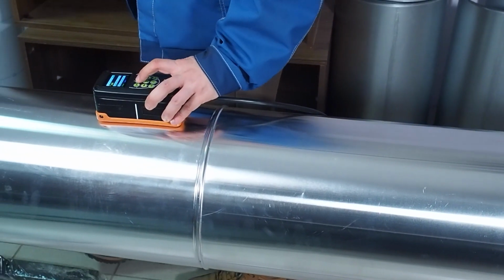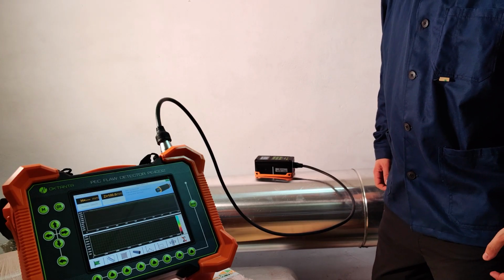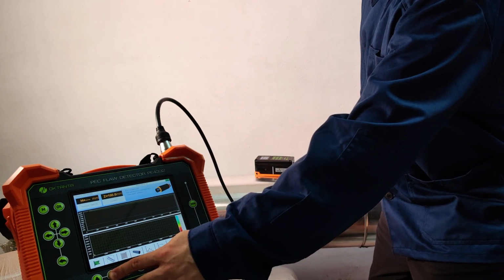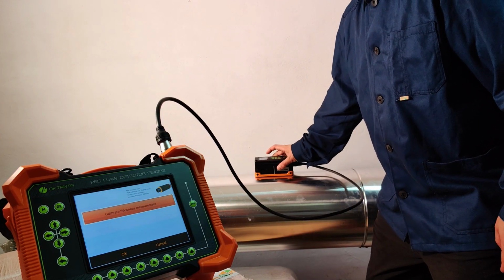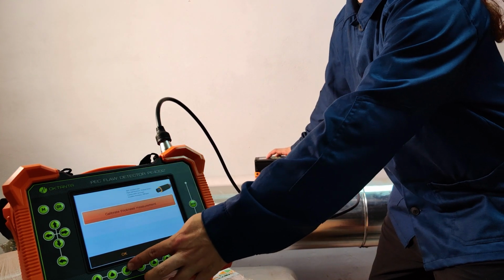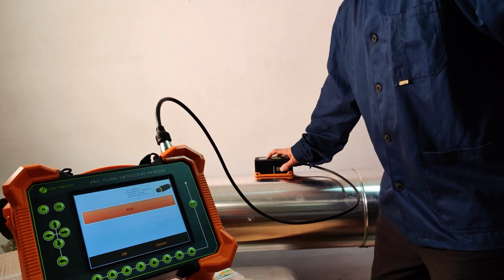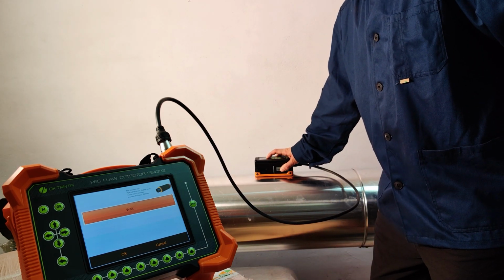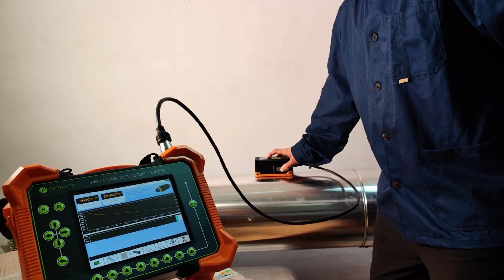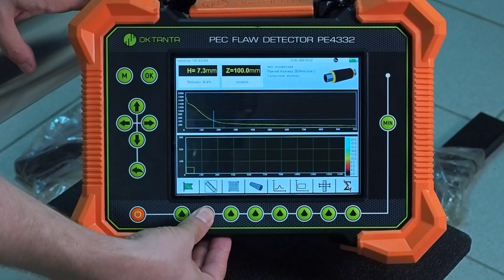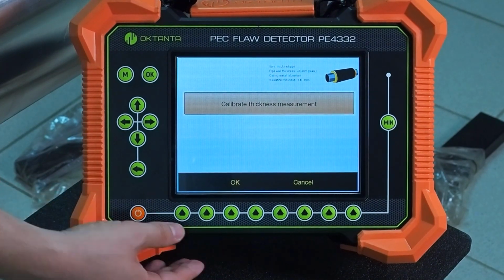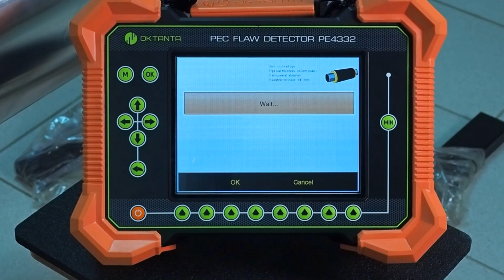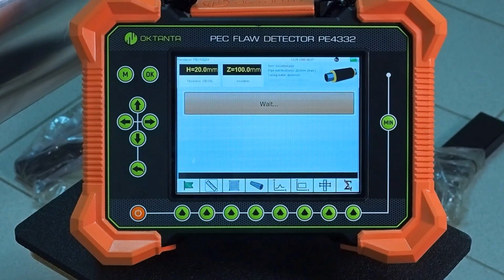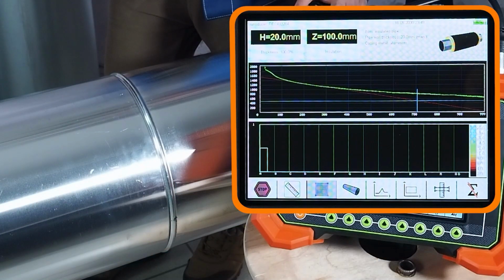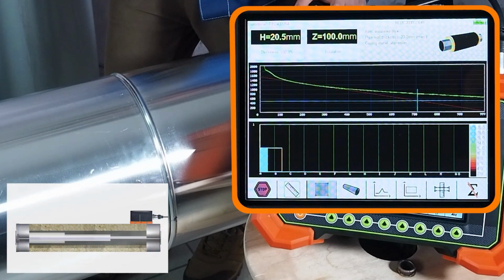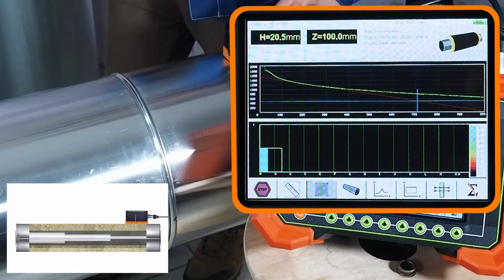in the areas with defects. And the final stage of calibration: let's install the sensor on the item at a point with no expected defects and, accordingly, with the wall thickness as specified in the data sheet. Switch the mode to calibration. The device will take several measurements and display the measured value and a diagram of the item demagnetization. Calibration is completed. The device will use this calibration data as a reference for further measurements.